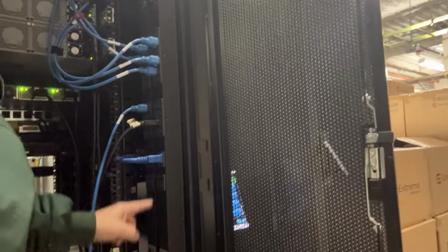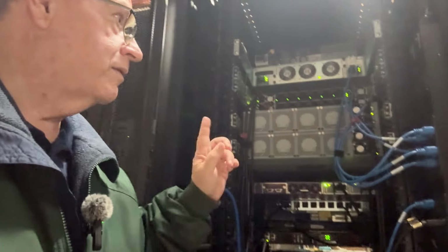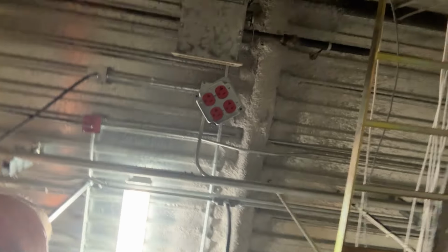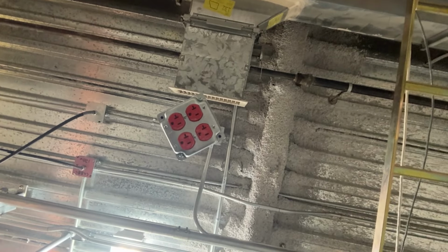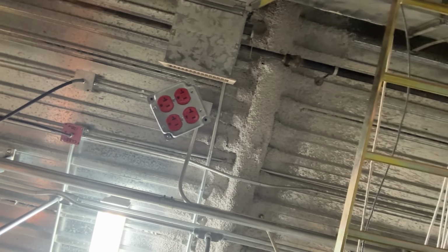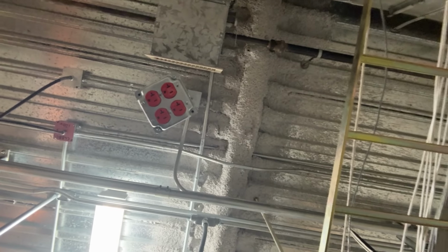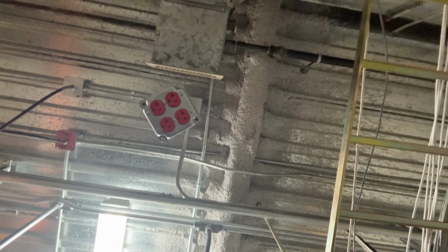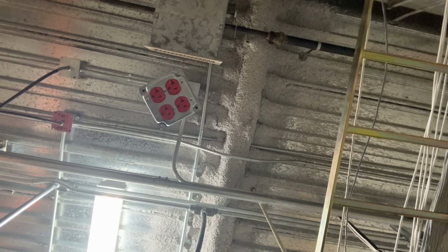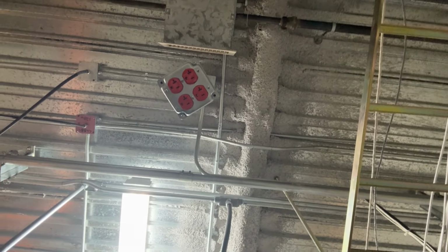Life was good, right? Life was good until today when it lost power, because this power strip here goes into facility power. Actually goes into e-power. So if you look up these guys, the red plugs, we call those e-power. Anything that isn't red like that doesn't go to our generator.